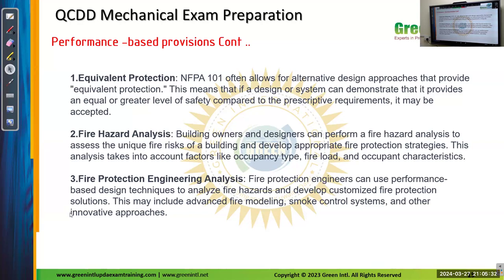Fire hazard analysis. The building owners and designers can perform a fire hazard analysis to assess the unique fire risk of a building and develop appropriate fire protection strategies. This analysis takes into account factors like occupancy type, fire load, and occupant characteristics. The standard which we are following may not identify the risk level in your building, because your building's application may be different from that of the standards. So you have to verify the hazard level, and based on that hazard level, you can propose a fire hazard analysis. Once it's done, you can develop fire protection strategies.